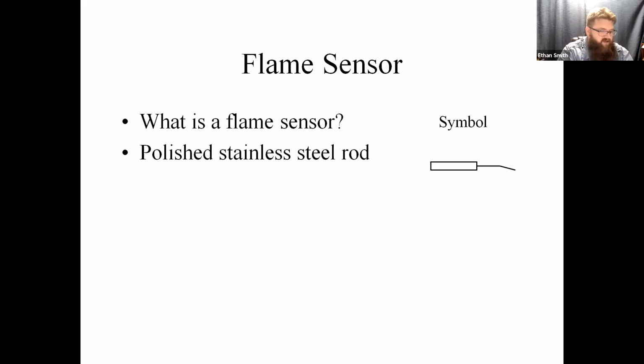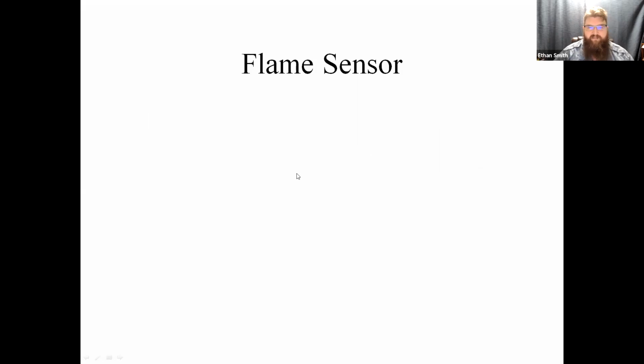So the worst flame sensors I ever saw were in a boiler that was in a dry cleaner. And anybody who's ever been into a dry cleaner knows that they use all kinds of chemicals in there. Most of them, by the way, are corrosive. We would actually go out and replace the flame sensor every year in this boiler, because it would eat away at the flame sensor so badly that it was unusable every heating season. Okay. How'd the heat exchanger look?